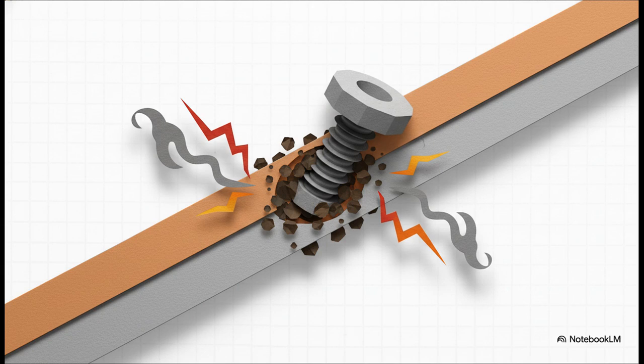All right, here is a massive narrative twist for you. Straight, continuous conductor bars, they almost never fail. The failures almost always begin at the joints. When a joint fails, it's usually because of a few sneaky villains creating runaway heat and resistance. We're talking loose hardware, long-term material creep, uneven contact pressure, and dissimilar metal galvanic effects, like when someone improperly bolts copper directly to aluminum. And we absolutely cannot forget rapid oxidation films.